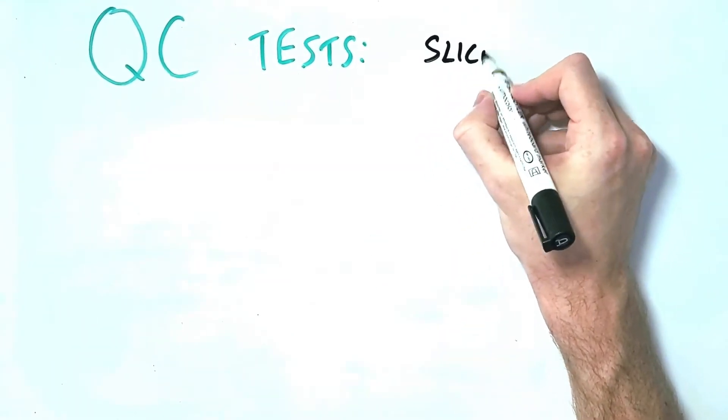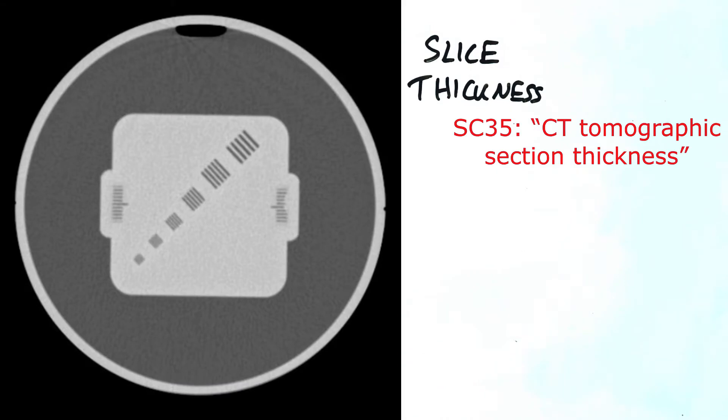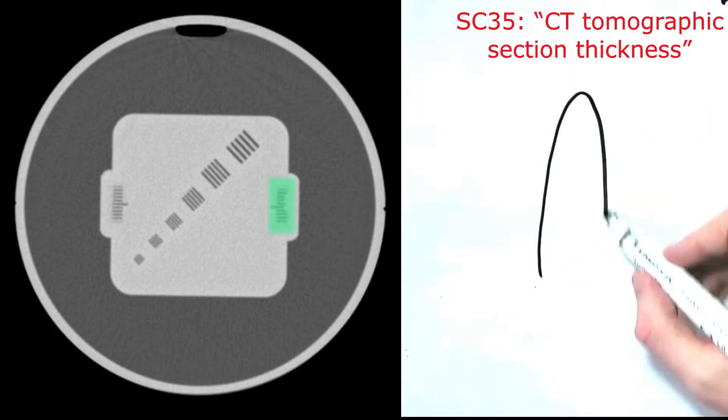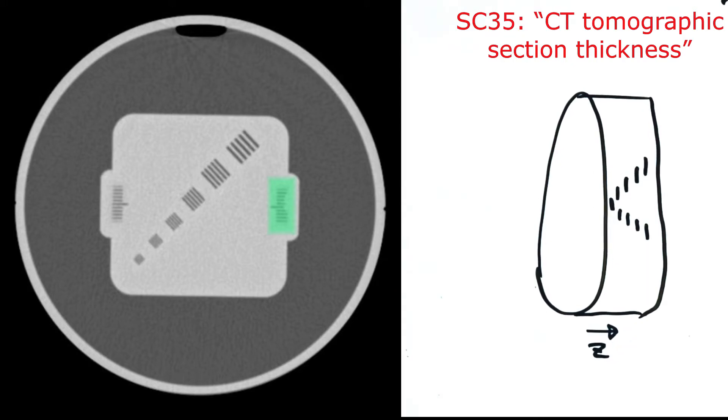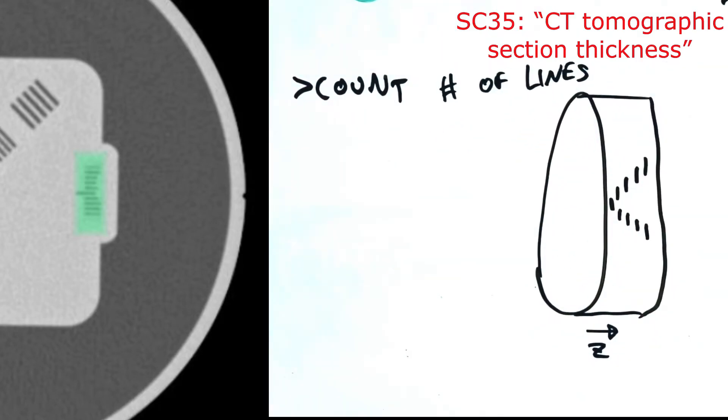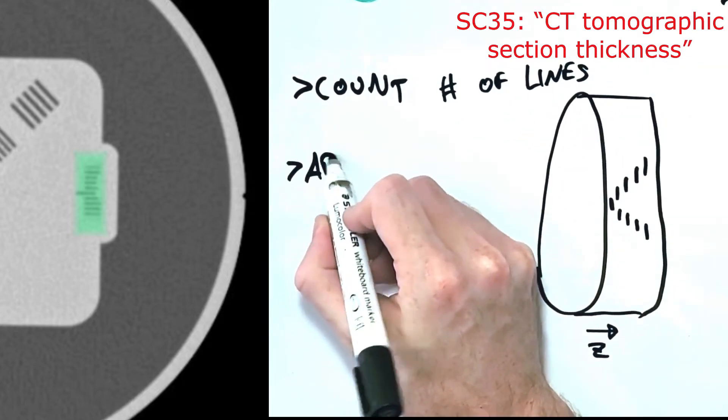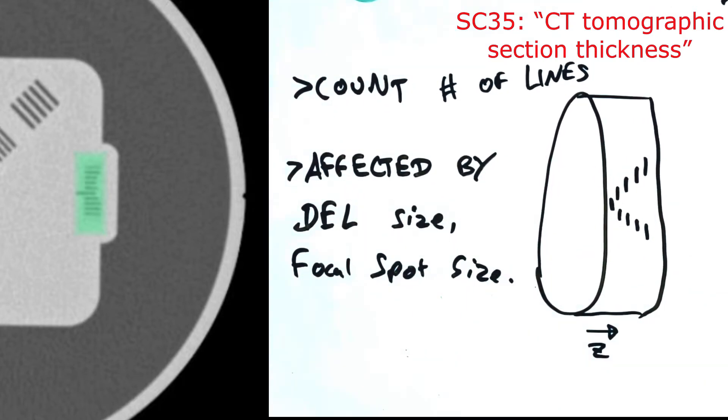Slice thickness can be measured by using a phantom with lines spaced at set intervals along the z-axis. So the phantom itself looks like this and if you were to look at this area from the side, these lines diverge along the length of the z-axis. So we can count the number of lines and assess how thick our slice is. The accuracy of the slice thickness relative to the selected value is dependent on the detector element size and the size of the focal spot in the tube. Slice thickness should be assessed monthly.